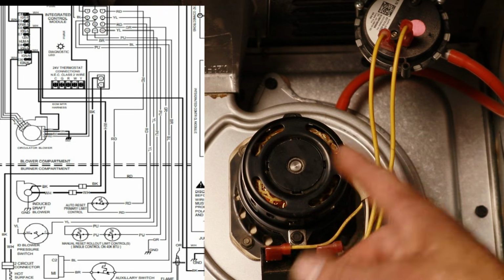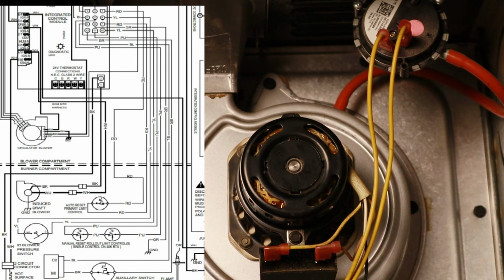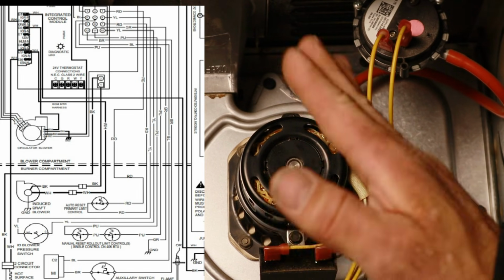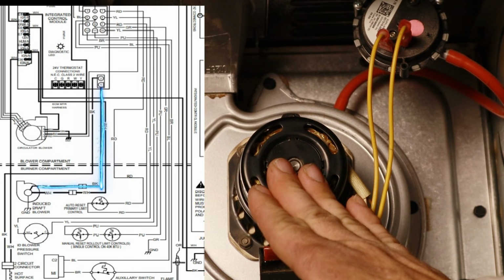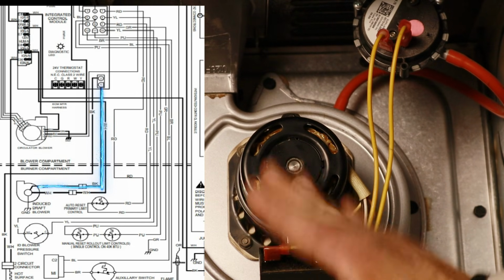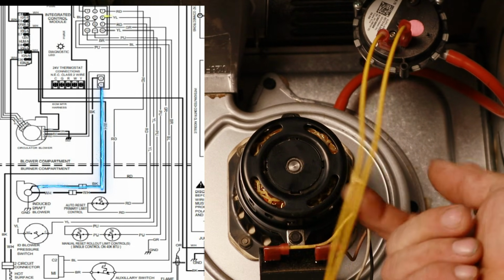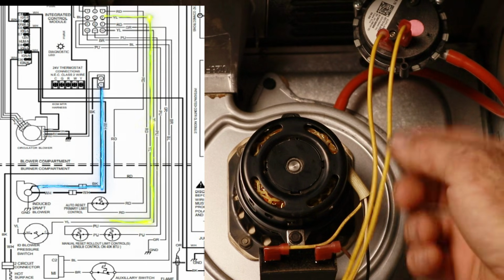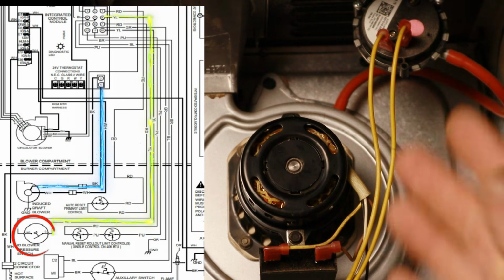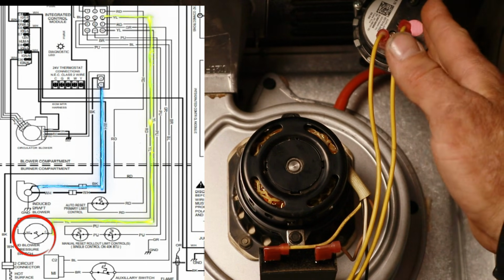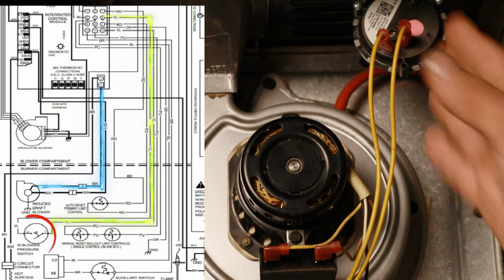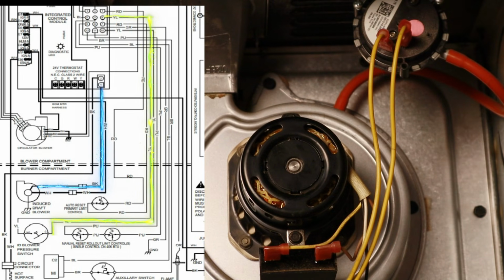So what we have here is our control board sending 120 volts up to this inducer motor to start the motor, and then it's sending a low voltage 24 volt signal up to our pressure switch. Knowing that our pressure switch is the next step in the sequence, we can go back, look at our schematic, try to find that pressure switch on it, and trace out that wiring as well.